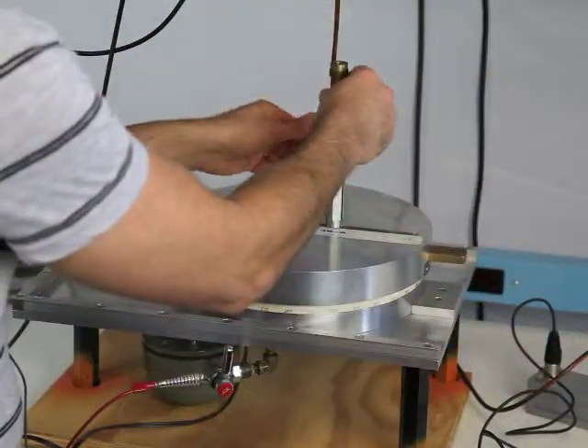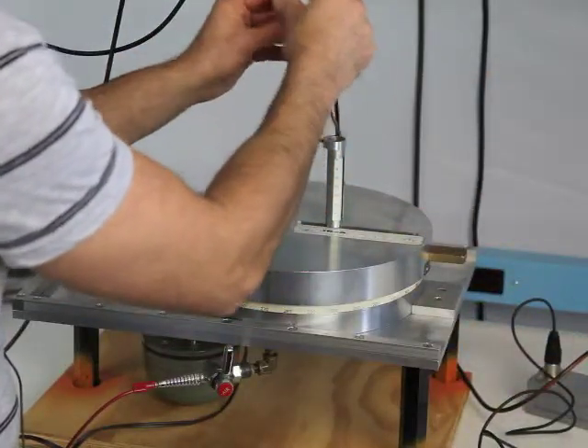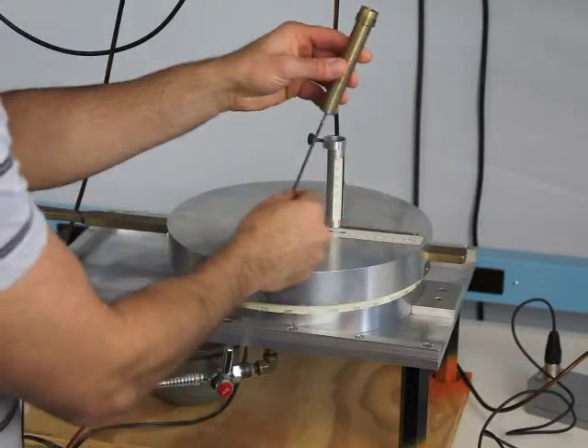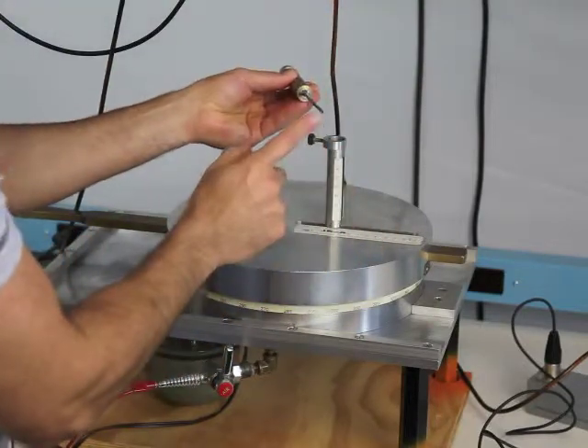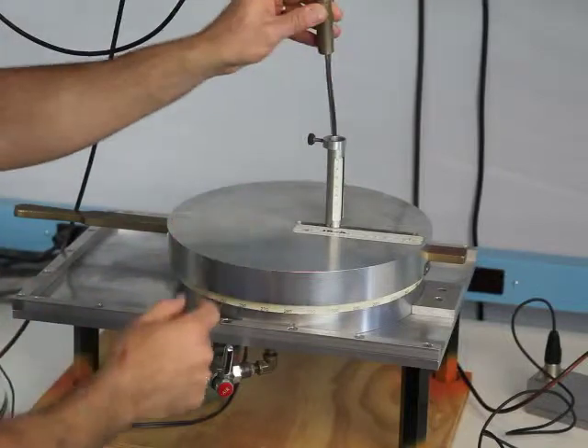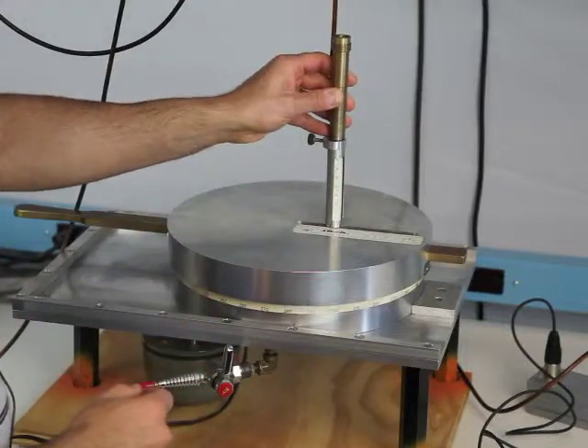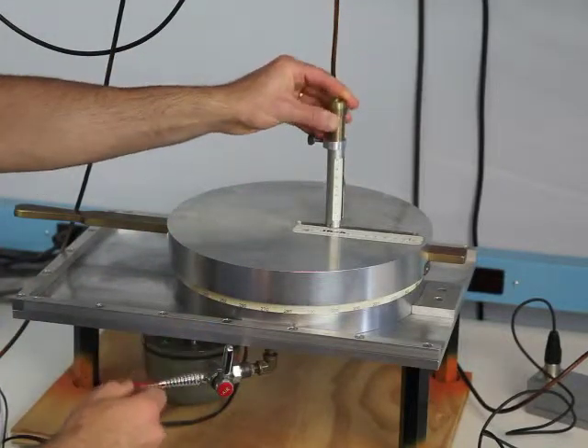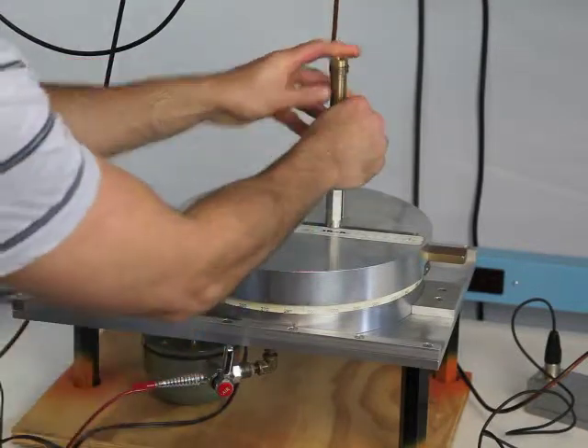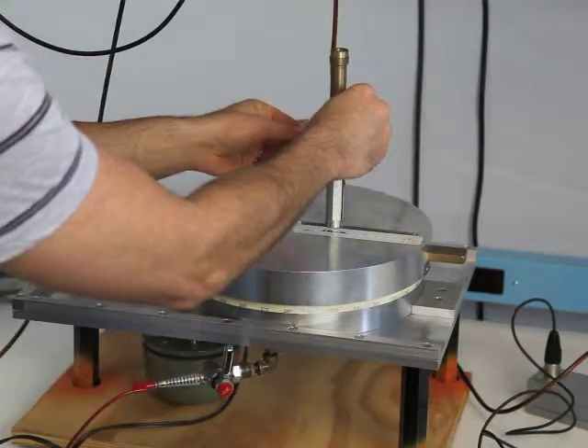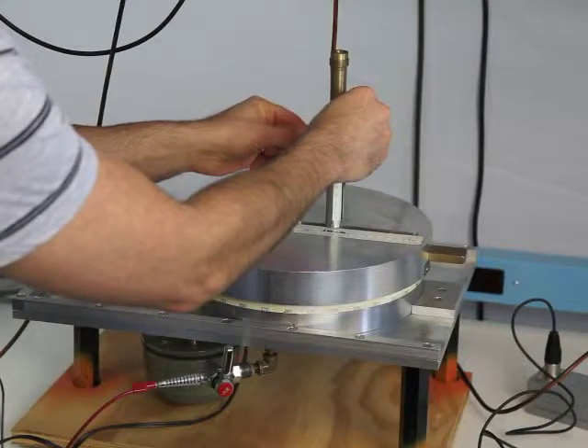And we have a sleeve here, or a probe, that the microphone slides into. It's got a little stainless steel tube here, which goes down into the chamber, and it allows us to, by moving it up and down, probe the Z-axis of the chamber.